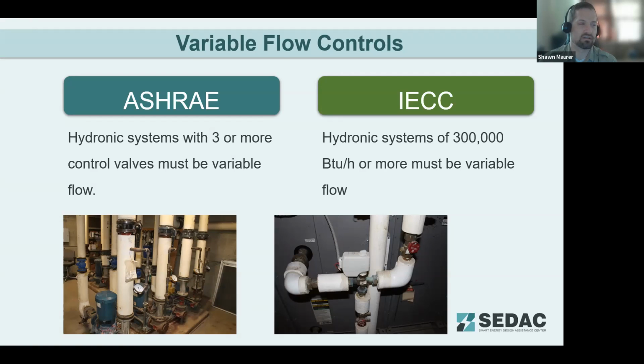And Ryan, back to your discussion of building additions and not having to update the HVAC system. We had a question come in, what if you're just replacing the HVAC equipment with an addition? And I think we touched on that earlier in my section, the big difference between ASHRAE and IECC. Yeah, the important thing there is if this is being dealt with for an addition, then if you're replacing the HVAC unit, you're into the requirements for replacing an HVAC unit. If it is like for like and you are using ASHRAE 90.1, then you're able to just do that replacement like for like. If it's IECC, then you do have to go ahead and make those improvements.